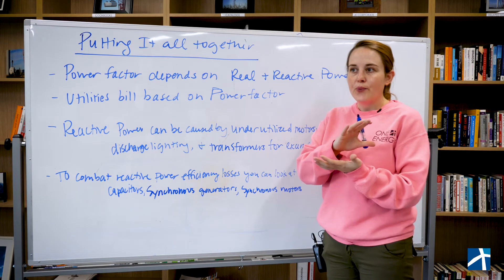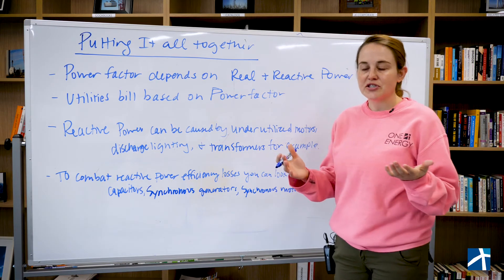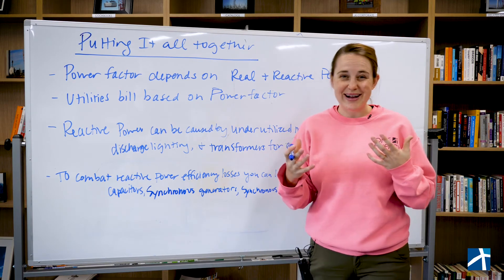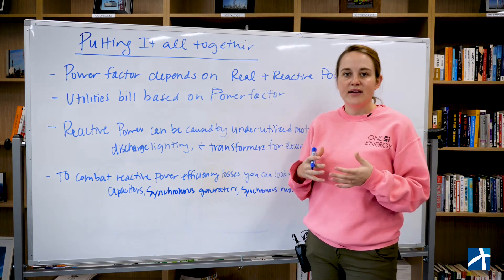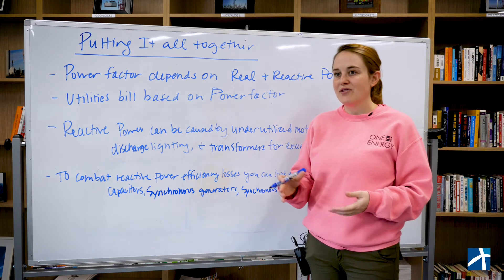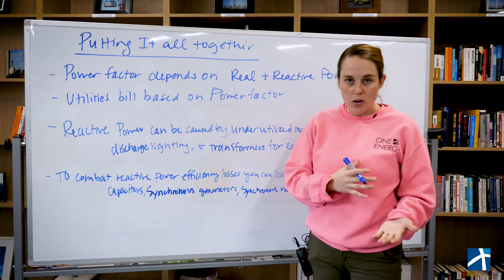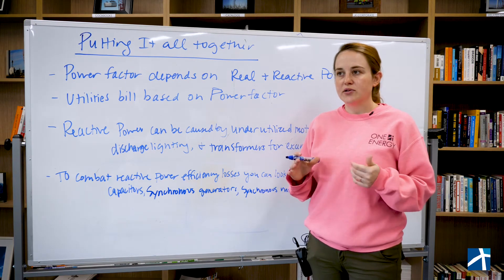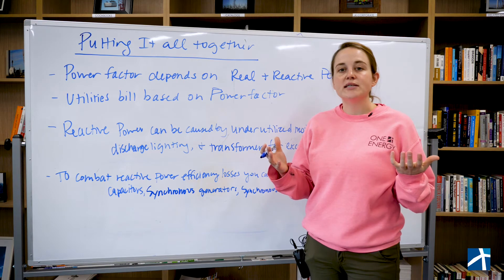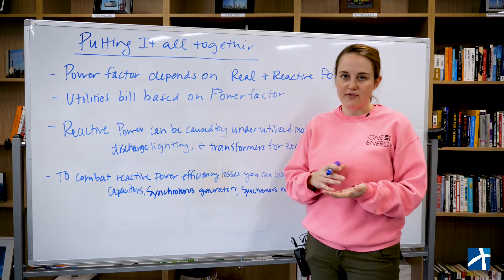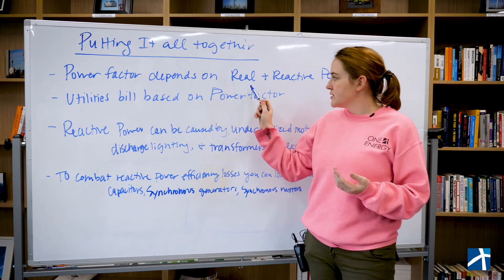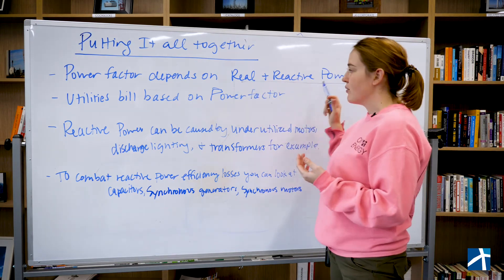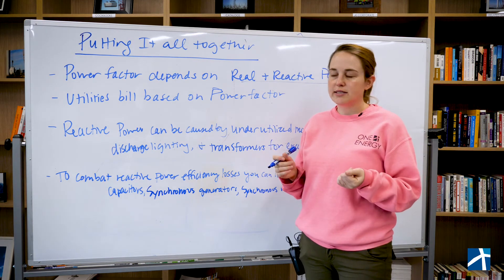When a utility sends their billing to you, for example, if your power factor is not at like 0.95, if it's lower than 0.95, they're going to bill you more because you have more waste or less efficiency in your system. That 0.95 seems to be a mile marker, but understanding your power factor, you also need to understand what real and reactive power is and where you may have that in your system.